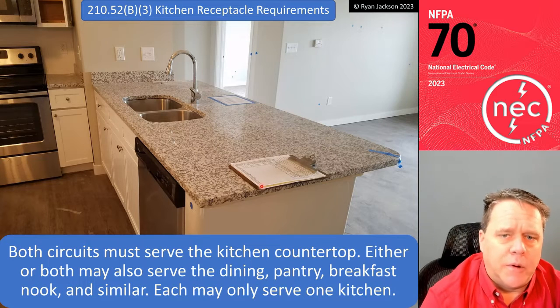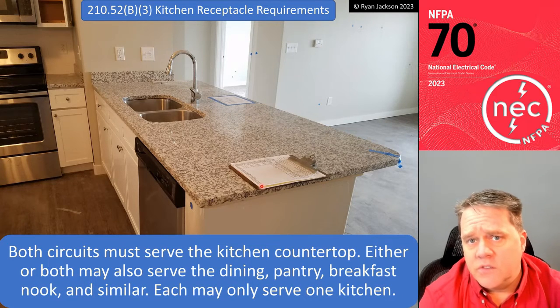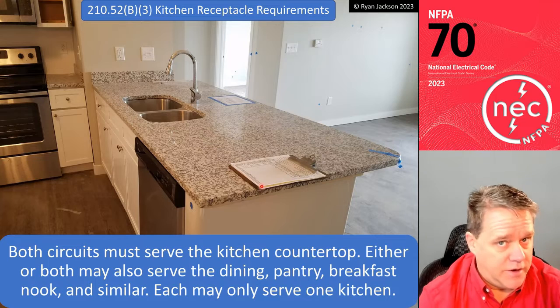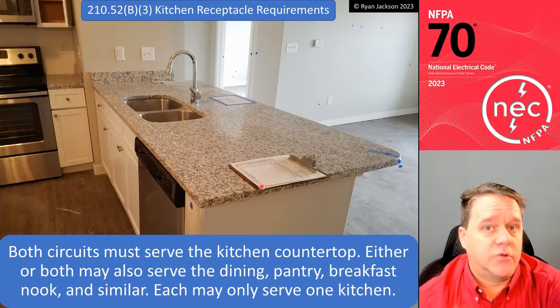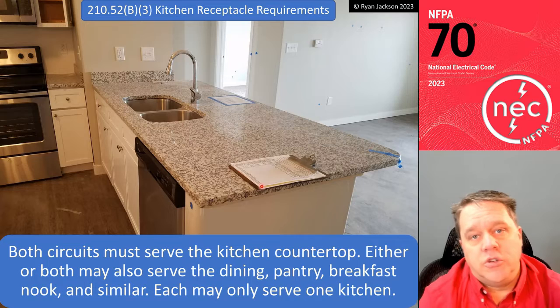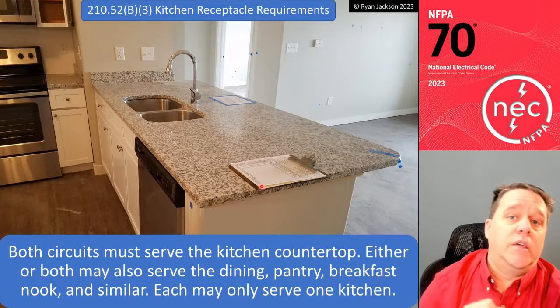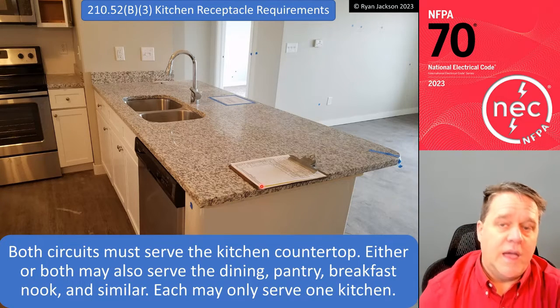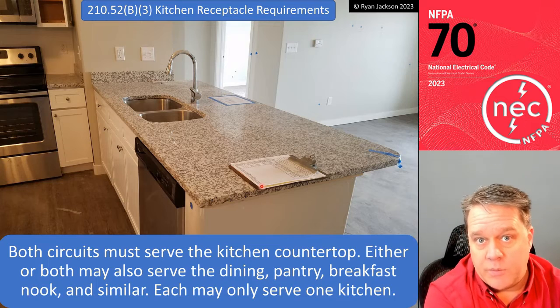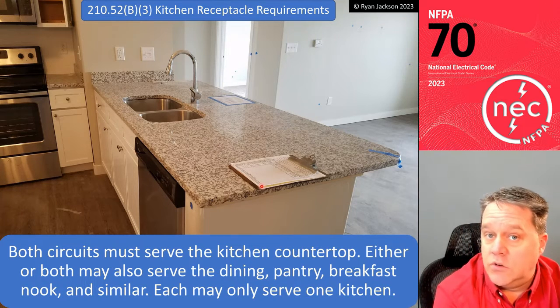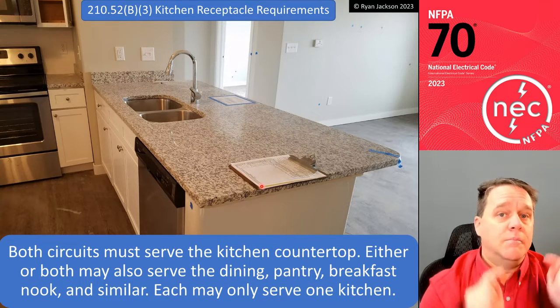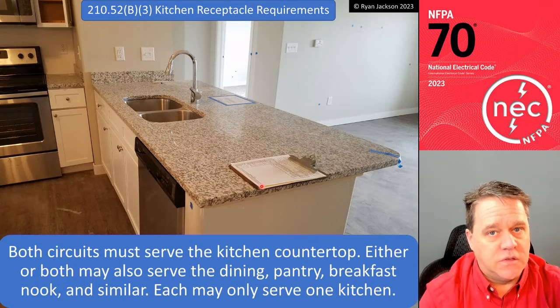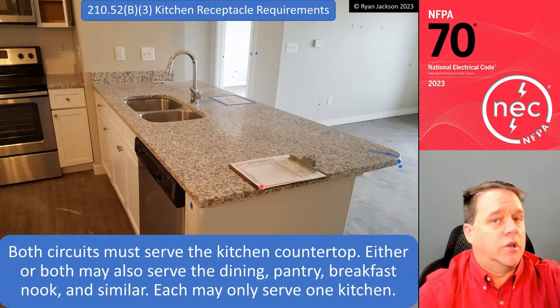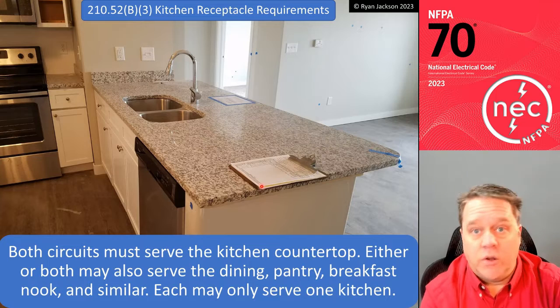All right, so remember, small appliance branch circuits have to supply the dining room, the kitchen, the pantry, the breakfast nook. So could you have all the receptacles in the dining room on one circuit and all of the kitchen countertop receptacles on the other? Well, the answer is no, because this rule says both circuits have to hit the countertop. Now, we're not going to go any deeper as far as telling you what to do than that.